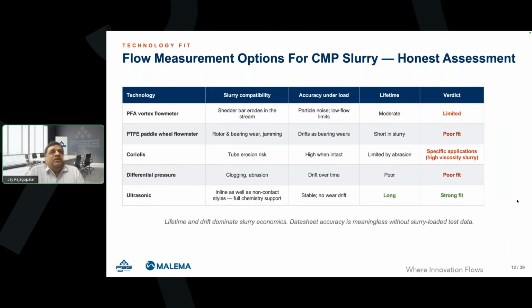The first technology is the PFA vortex flow meter. It has a shedder bar, which actually obstructs the flow. It uses vortex shedding as the means to measure the flow, and the shedder bar would erode, so that would not be an ideal choice for slurry applications. In the past three decades, paddle wheels were also used in those applications. If you look at older 200 mm, 150 mm CMP tools, you will find paddle wheels. Obviously, they have rotating parts, and they can drift, jam, and shed particles, and hence it's really a poor fit. The newer tools do not have them.